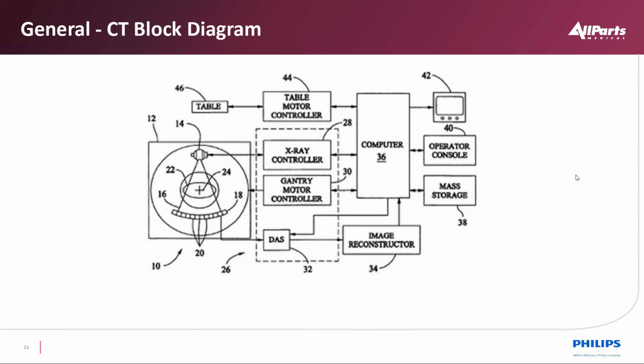And so we have to deal with an X-ray tube, an X-ray controller. We're spinning the gantry. We're also moving the table at the same time, and we're under computer control to manage all this. And then we have the operator that basically decides which algorithms are to be used. Okay, we pick which filters, where the table needs to be, start, stop, the slice thickness, all of that done in our protocols. That's sent to the computer, dispersed out as a job. And then we have 2 types of images. We have the raw data image that's in the image reconstructor chassis, and then we have the mass storage of a completed DICOM image. So the DICOM images are already processed data, whereas the raw data we have in the image reconstructor is data that we can reprocess again with different algorithms.